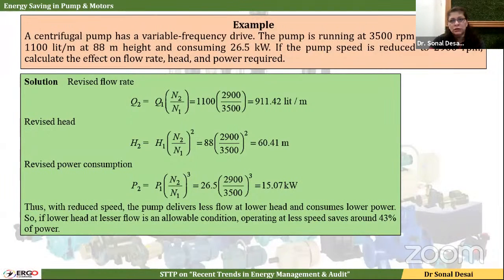If we reduce the speed to 2900 RPM, then what change is going to occur in the performance of the pump? That is shown over here. By reducing the speed from 3500 to 2900, we can see that the flow will be reduced. Initial flow was 1100 liters per minute, which is getting reduced to 911. In the same way, head, which was 88, reduces to 60 meters due to the reduction in speed. And power, which was 26.5 kilowatts, has now dropped to 15.07 kilowatts.